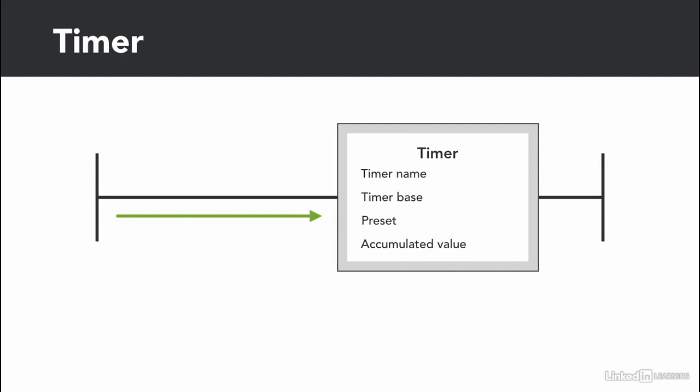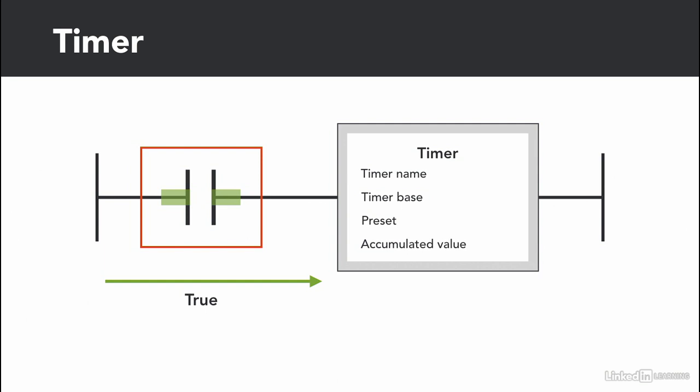A timer resets with a change in the rung condition. So if the rung is true, the timer starts timing. Once the rung goes false, the accumulator resets. So if we don't have any input, then the timer will not reset unless the rung goes to false. But once we add an input, then the timer starts timing when the input is true and once the input goes false, the timer resets.